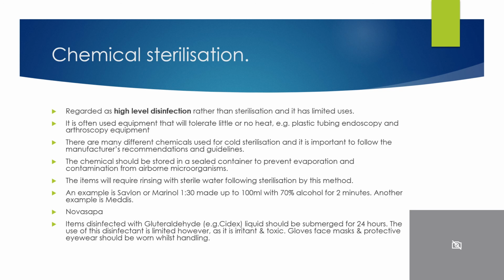An example is Savlon or Marinol 1 to 30 made up to 100 ml with 70% alcohol for 2 minutes. Another example is Meddis. We may also utilise Novasapa, although that is now hard to come across. In the past, when we used glutaraldehyde such as Cidex to disinfect, the liquid should be submerged for 24 hours. The use of this disinfectant is limited, however, as it's irritant and toxic. And if we were to use, then gloves, face masks and protective eyewear should be worn when handling.